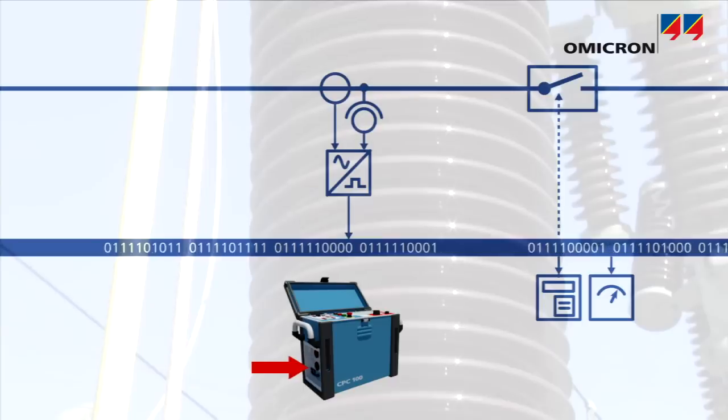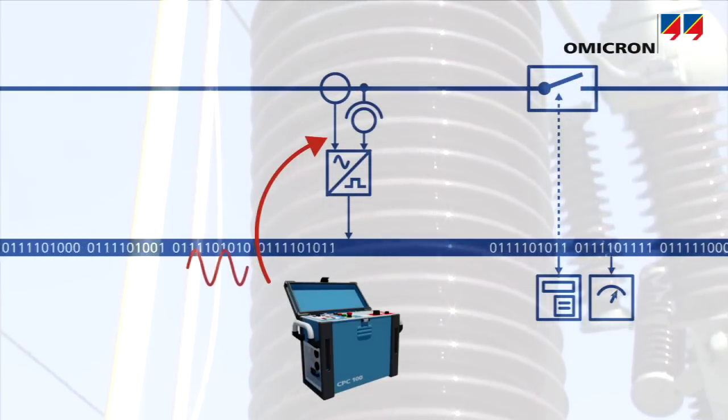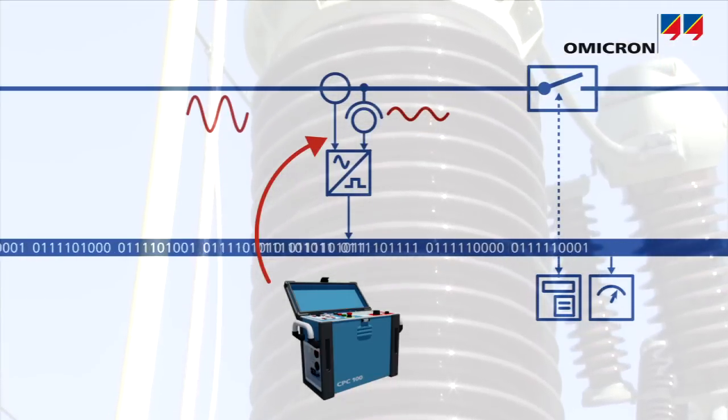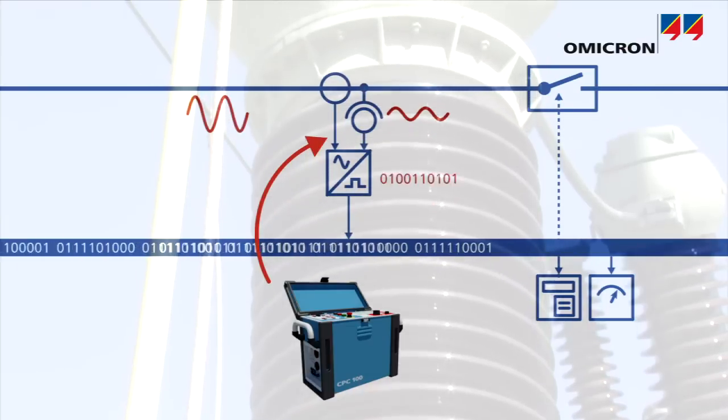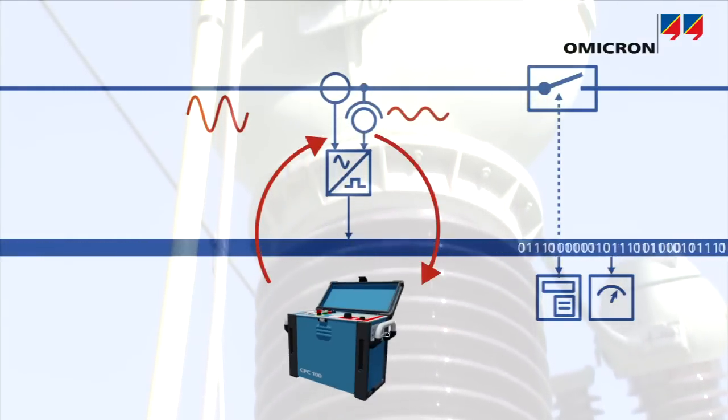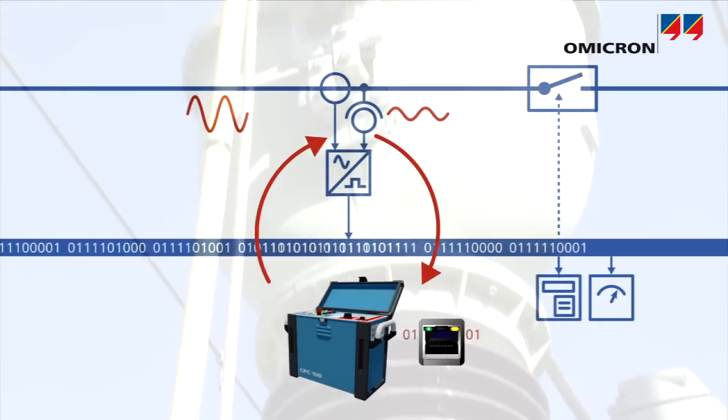The CPC's high voltage and high current outputs are used to apply test voltage or inject test current on the primary side of the CT or VT. The sampled value stream that is generated and published to the network by the merging unit is read back via the CPC's network interface and compared to the injected primary values.